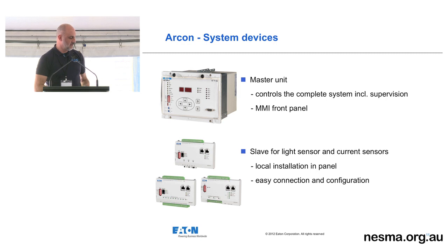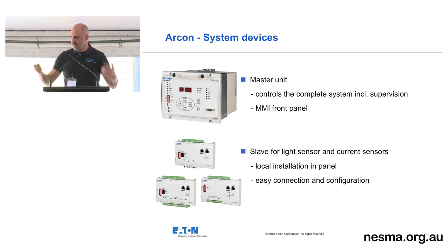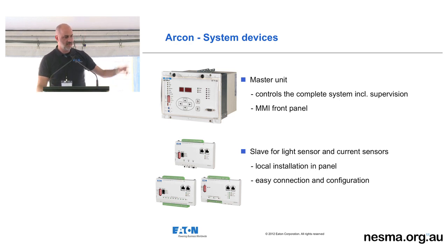The architecture of the system, the pieces that fit into this puzzle, starts off with a master unit. That's the brains of the system. Not only is it the brains of the system, you'll see a whole lot of indicating lights in there. It's self-diagnostic, so every now and again it self-monitors. So you do have fault signals on the front there if an event were to occur. The slaves are part of the system as well, so they're spread around the board. The reason you have slaves is they only handle a certain amount of outputs per slave, in terms of how many optic fibres you can take out of each slave. You can do it as a linear optic fibre, or you can do them as point sensors around the switchboard.